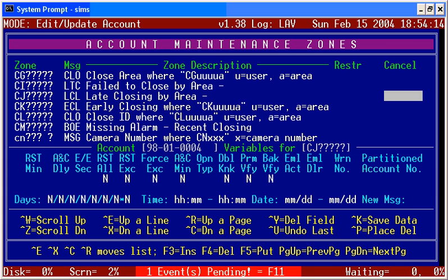Most opening closing signals, bypass signals and such should always be left up to the zone account. In the base account, you only want those zones that are indigenous to that particular panel, so that if your dealer or your installer put in just 8 zones in that panel for different places in the house, you want to identify those 8 zones. But you don't want to identify panel tampers and battery signals and power signals and wireless test signals or all kinds of tests, let those always go to the zone account.